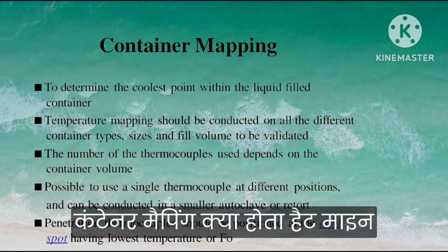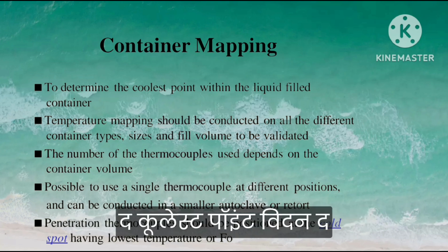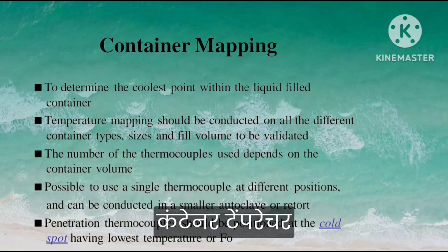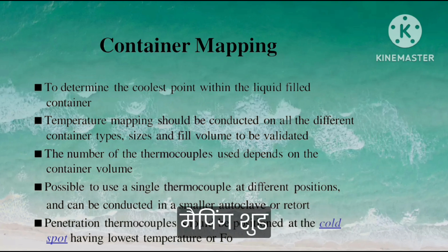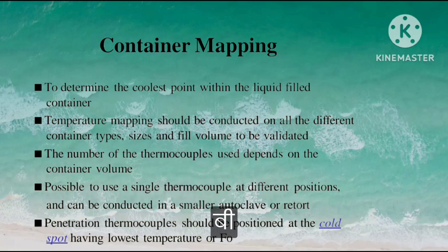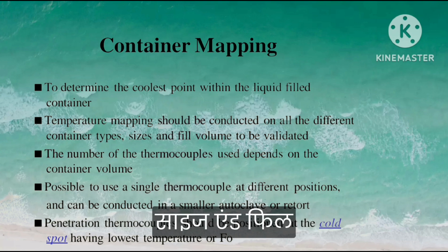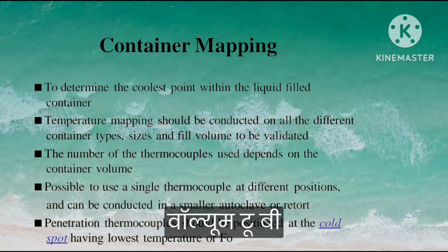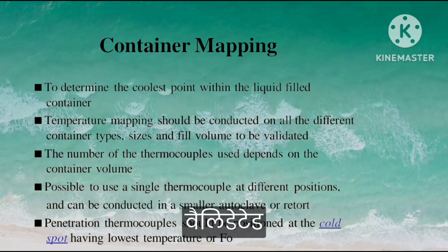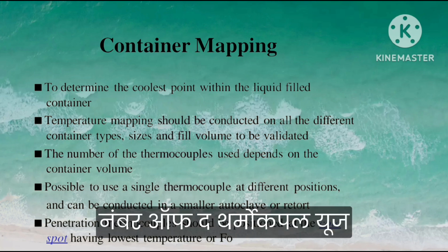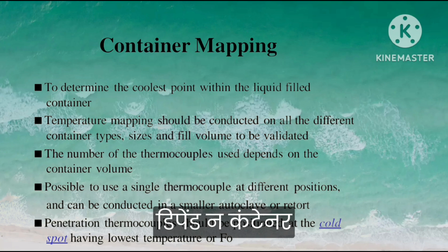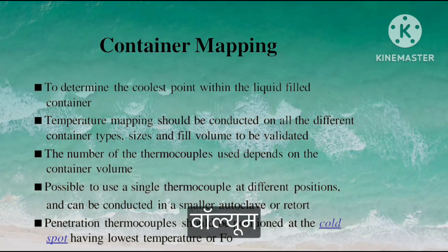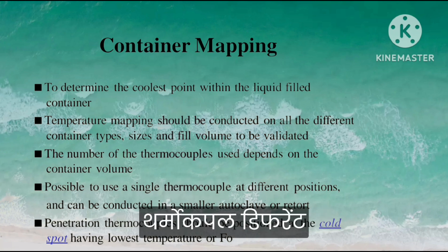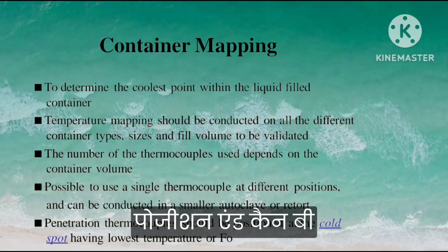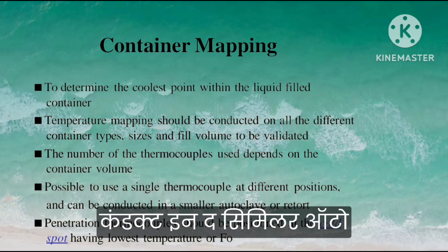Container mapping क्या होता है? To determine the coolest point within the liquid filled container. Temperature mapping should be conducted on the different container types, sizes and fill volumes to be validated. The number of thermocouples used depends on the container volume. It is possible to use a single thermocouple at different positions and it can be conducted in a similar autoclave or vessel.